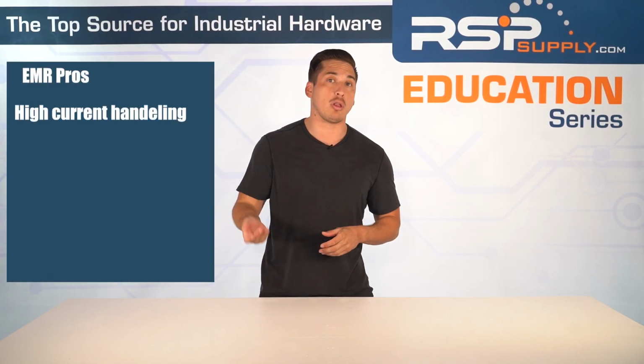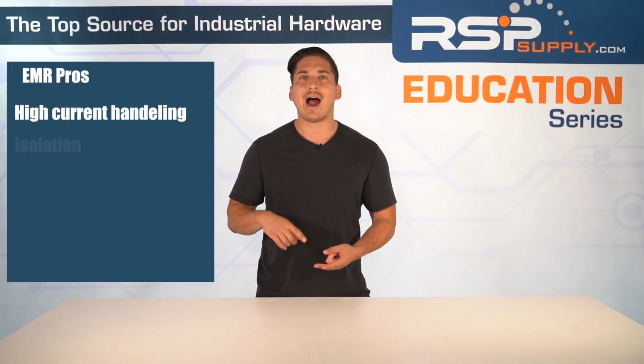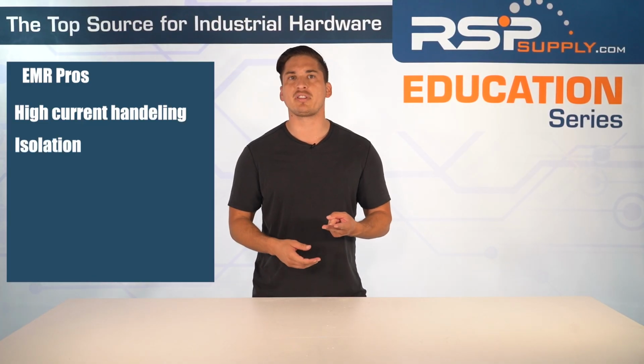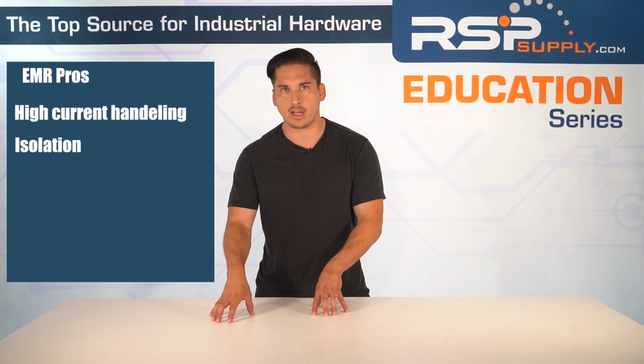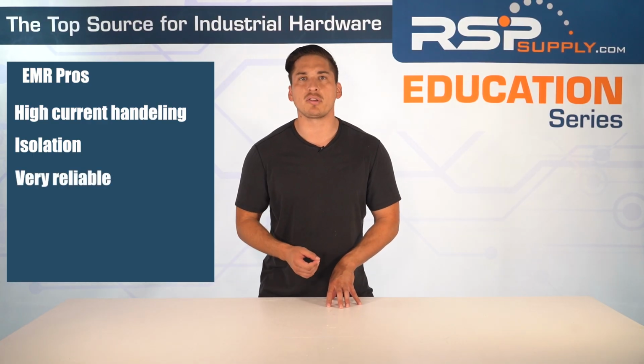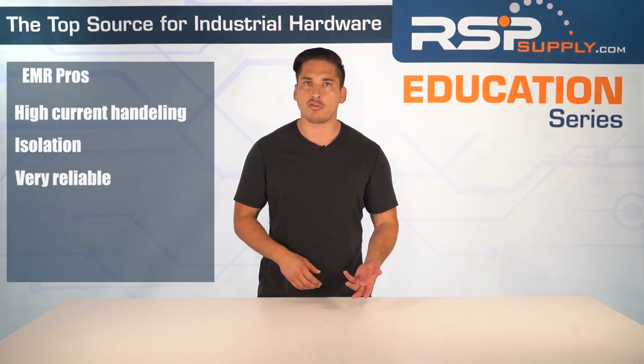Some pros of electromechanical relays: high current handling. They can switch larger loads up to 30 amp or more. Isolation. It provides strong electrical separation between control and load circuits. Very reliable for high voltage switching, used in motor starters, industrial machinery.